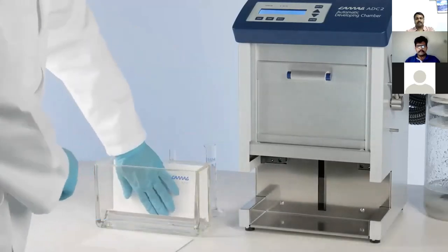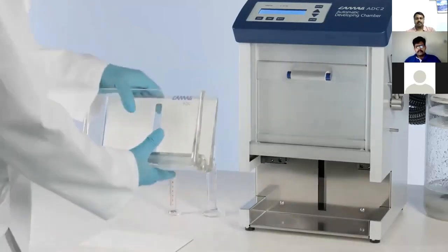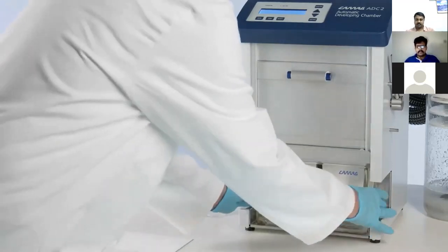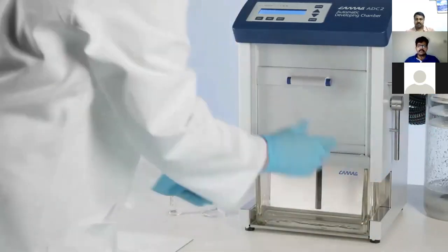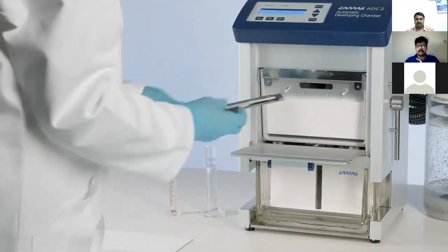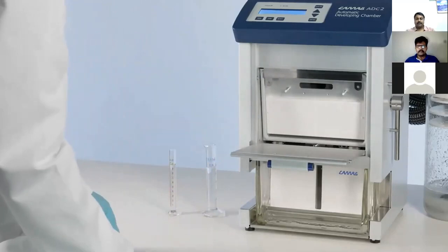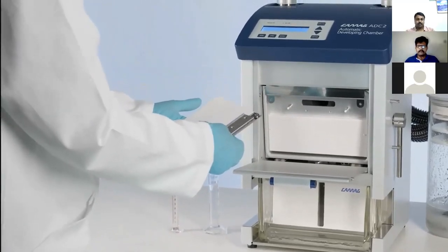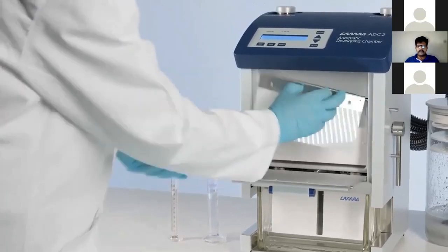The ADC2 will automatically develop the plate, leaving the analyst free to do other work. It's a Whatman filter paper, which is kept on the backside to saturate the chamber with mobile phase vapors for equilibrium. Open the front door, load the applied plate in the plate holder and insert the plate into the automatic developing chamber. It is not affected by environmental parameters. Then you put your plate in such a way into the ADC2.